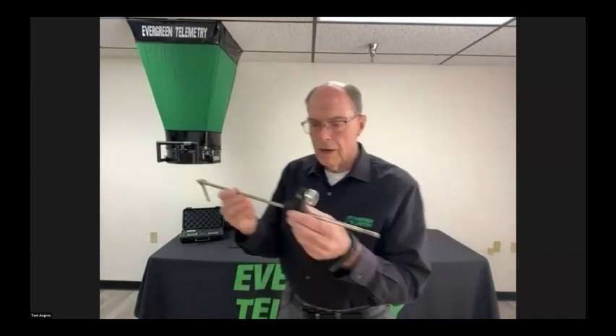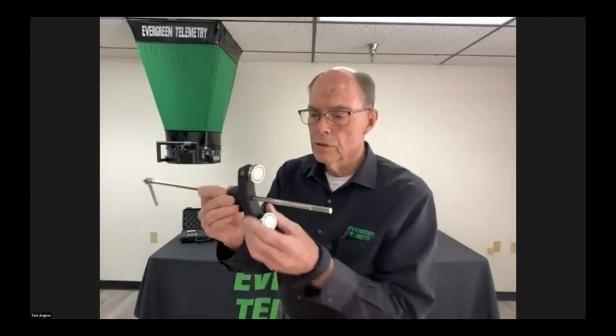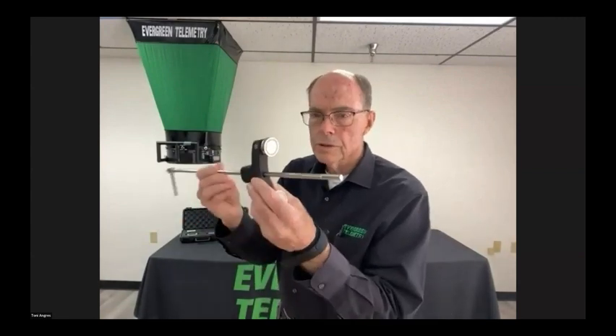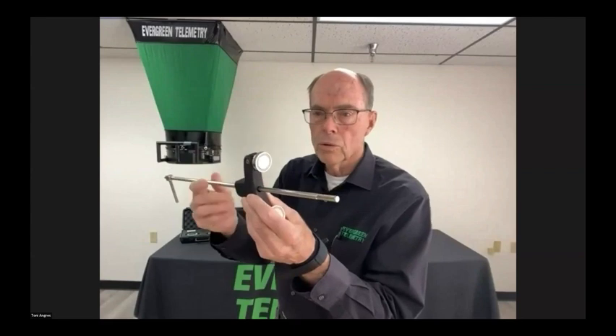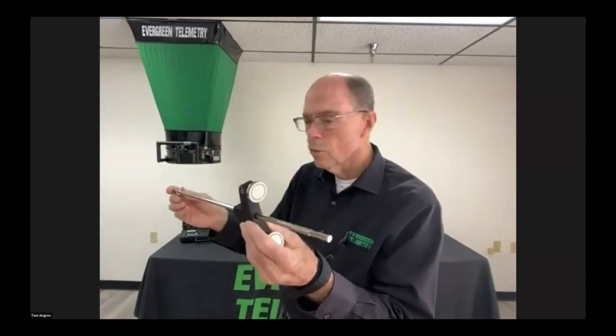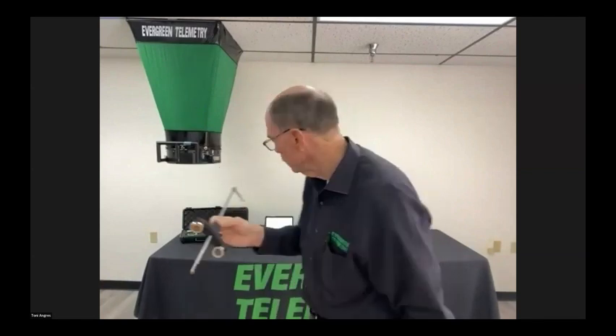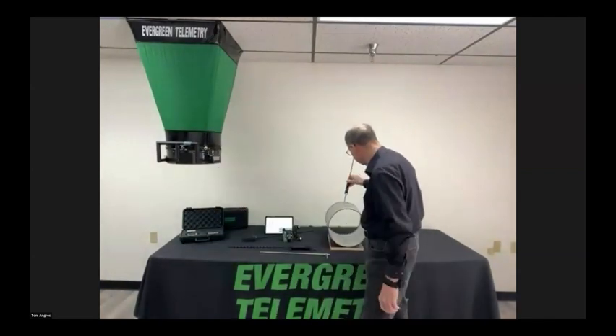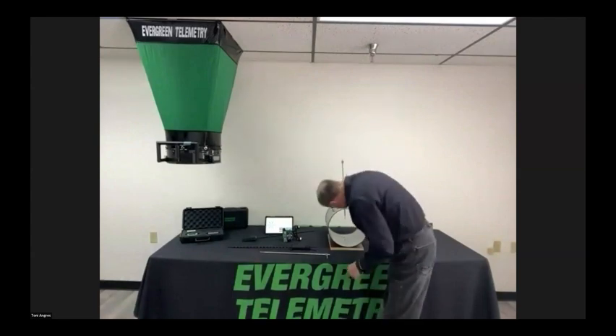One is what I call the guide lock. It's got 2 purposes: one is so that when you're doing a traverse, you'll be properly oriented and the tip won't be wavering around. The other is, imagine you are going to make a change to a fan or a damper in order to affect a change in the CFM. What you can do is set this up like this.